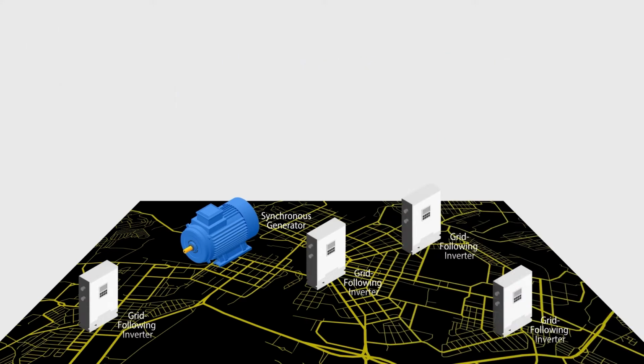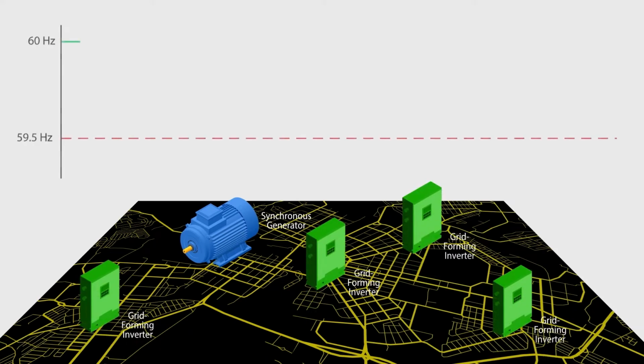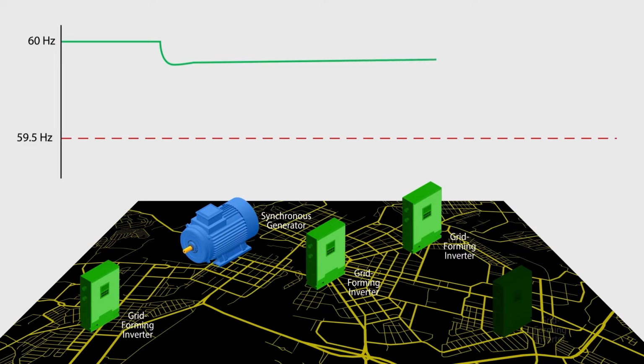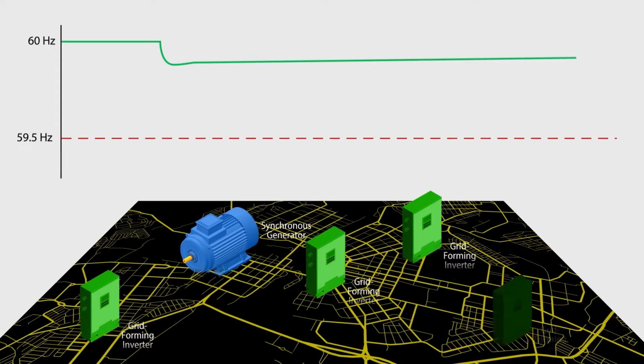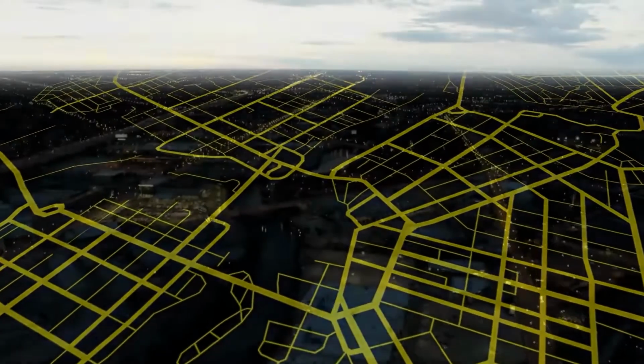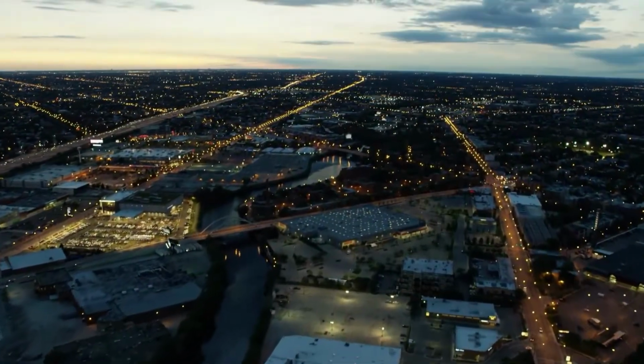Now, imagine that all grid-following inverters are replaced with grid-forming inverters. This time, when a lightning strike takes out an inverter, the grid-forming inverters react fast enough to stop the frequency from falling to the point where the grid sheds load. The grid remains stable, and the remaining resources rebalance the frequency to 60 Hz. Grid-forming inverters are essential to preventing outages.